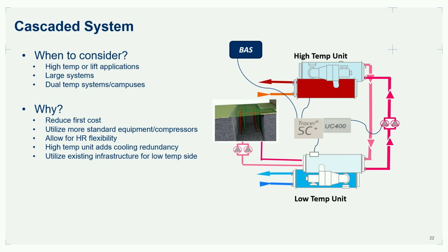Also, dual temp systems. Let's say maybe out of our central plant, let's have a decentralized cascade. Let's put 120 out of our central plant, and maybe those 3 labs on campus need 200 and there's nothing you can do. Let's put a booster in that basement, right? Put that 120 in the evaporator of a booster in that building alone, and then get your 200. Let's not drive the whole system to 200 when we don't need to, right?